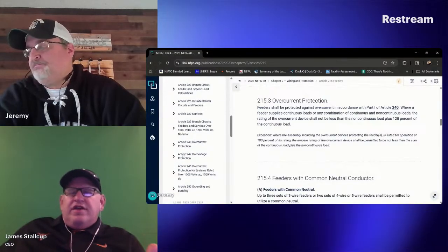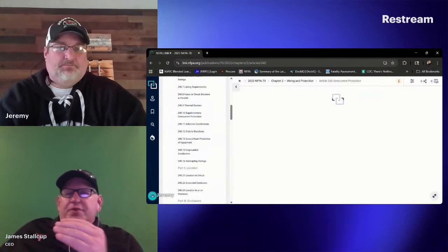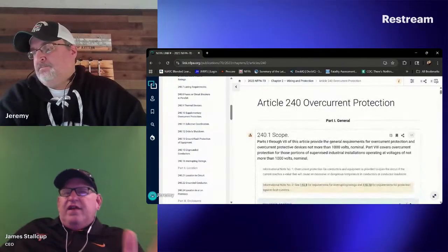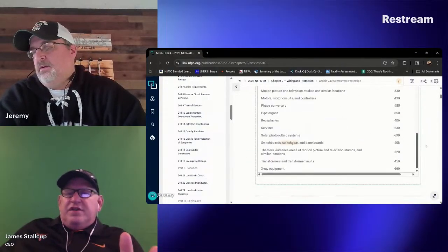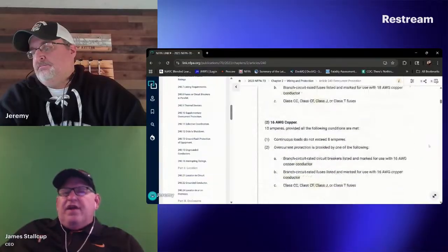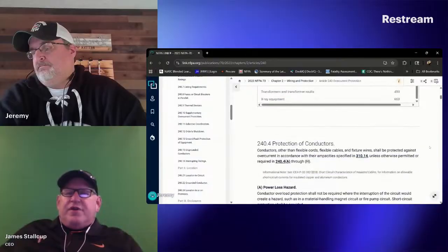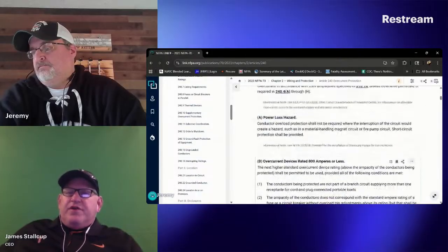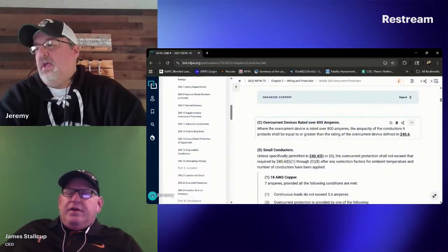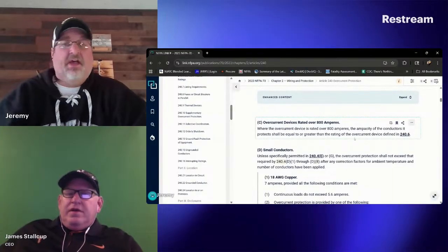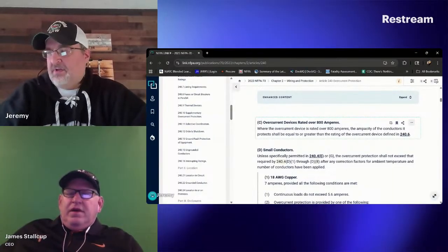And then you guys over there completely disregard the fact that if I go look at an AC unit and it has a HACR breaker rating, they have a minimum and maximum on there. You're basically telling the rest of the industry we're all a bunch of freaking idiots because we don't agree with y'all. Where does this say that I go down to the next standard size, or anything in 240.4C?